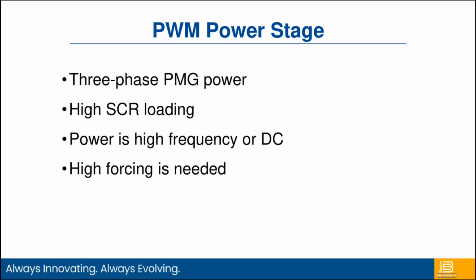An SCR-based power stage also may depend on the zero crossing of the sinusoidal waveform to know when to gate on. If we have noisy power input, with a lot of harmonics, high SCR loading, things like that causing a lot of noise on the AC input, they can cause false triggers. Our SCRs fire at random times, which can cause some instability issues. Again, because of the topology of the PWM power stage, we're not as likely to have any misoperations because of the noisy input, because we're just storing it as a DC in that bulk capacitor.